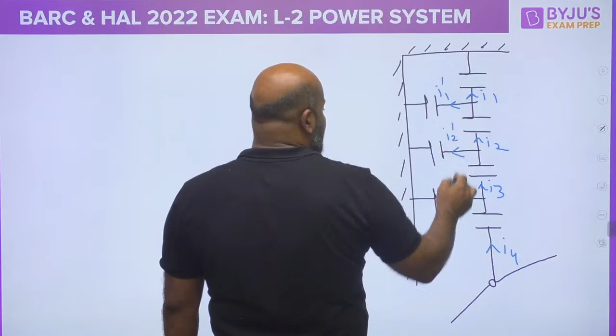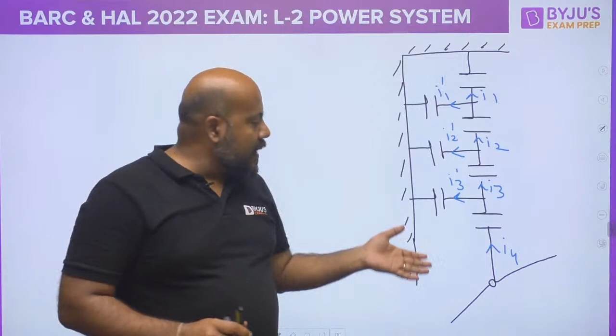Suppose this is the situation with 4 insulator discs and pin-to-earth or shunt capacitance, also called stray capacitance. The currents are I4, I3, I2, I1, with charging currents I1 dash, I2 dash, I3 dash. Because of these charging currents, the current in different segments of the insulator string differs, even though the capacitances are the same, so their capacitive reactances are also the same.